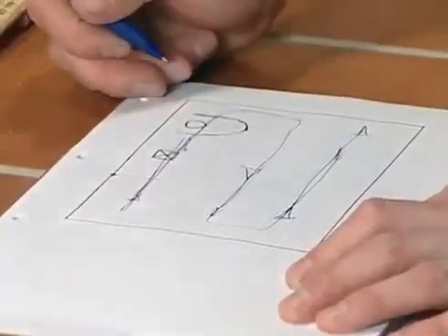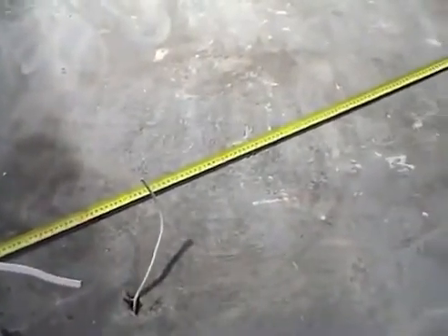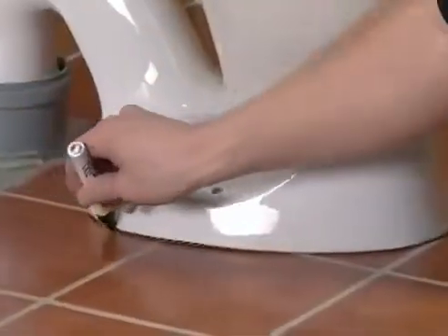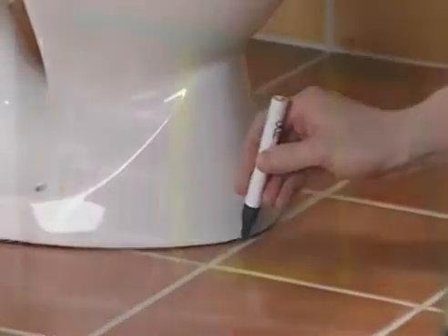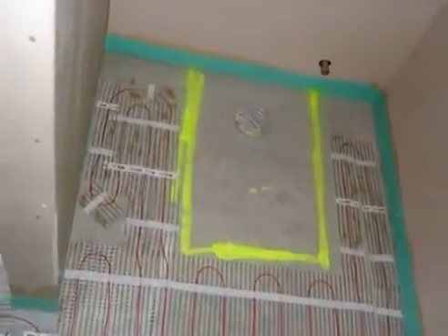Start by making a drawing of the room and measure the area where you will need the heating mat. The mat should not go under any permanent fixtures like toilets, vanities and baths, so you should not include these when calculating the heating area.